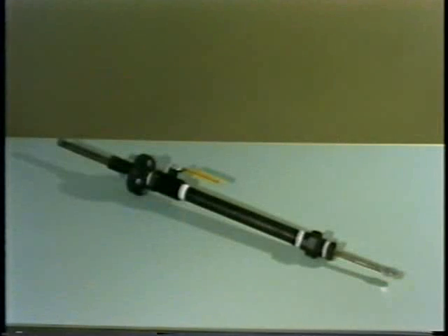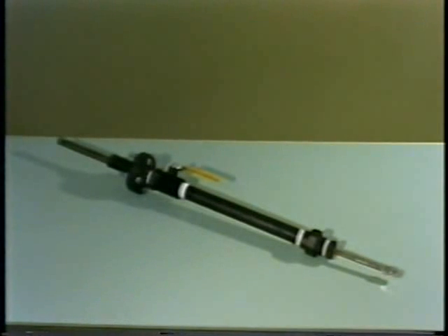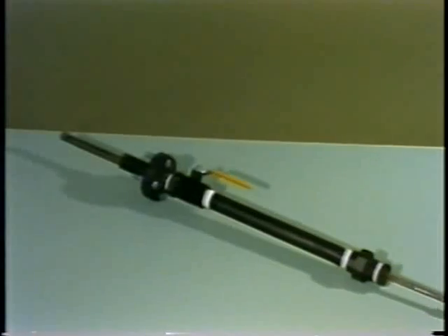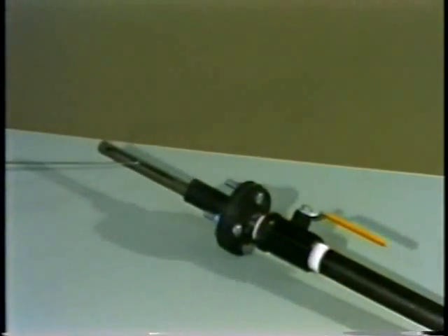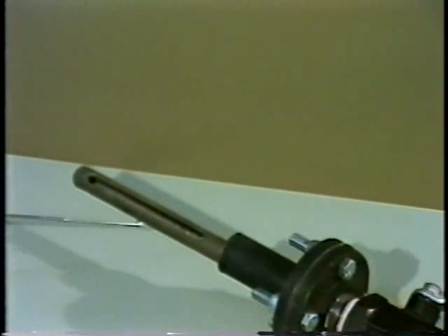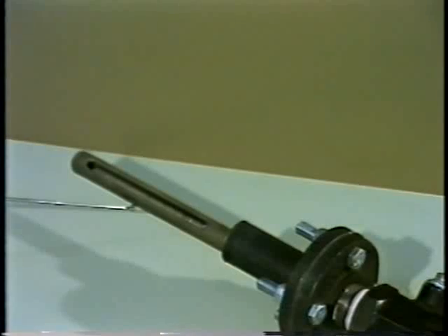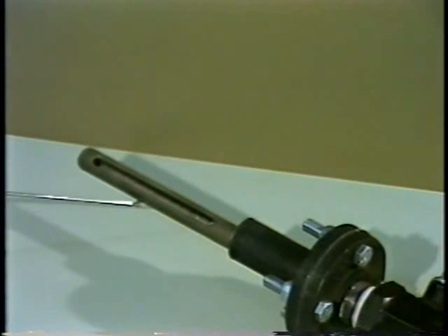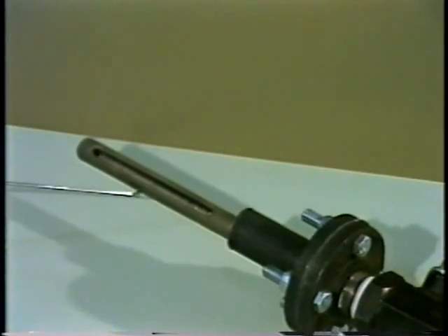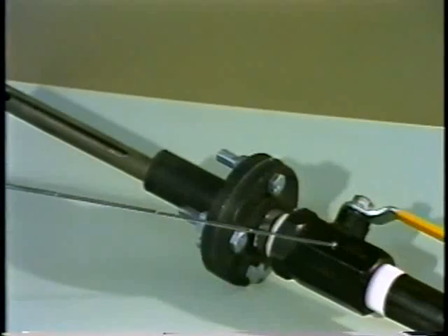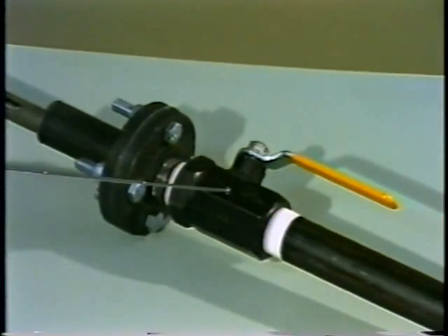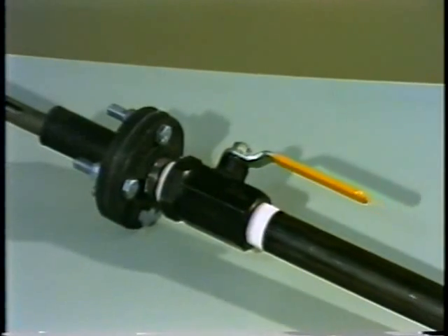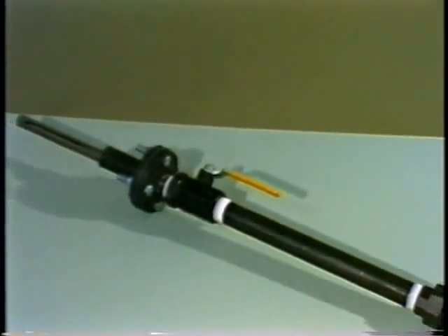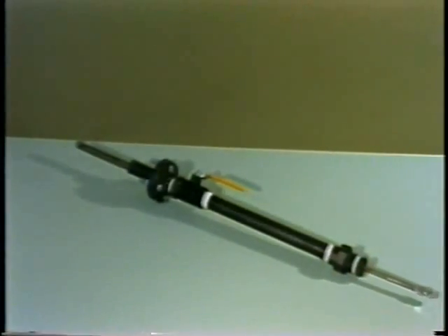The probe assembly is a crucial factor in the success of our system. Its purpose is to allow delivery of particle-free sample gas from a highly particle-laden, erosive environment. Blocking the coal particles is a sintered stainless steel filter, which is housed in an erosion shield. The erosion shield is plasma coated by a proprietary process to withstand the erosive mill environment. The ball valve and V-seals allow removal of the probe while the mill is in operation. Erosion shields can perform up to 2 years or more without replacement.